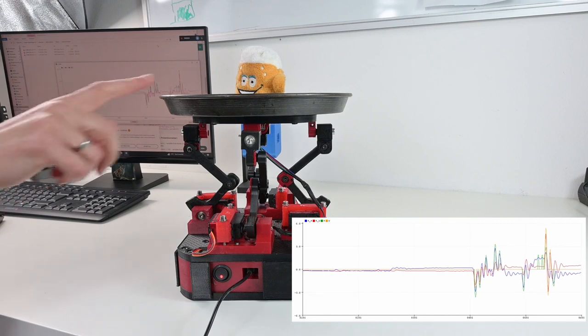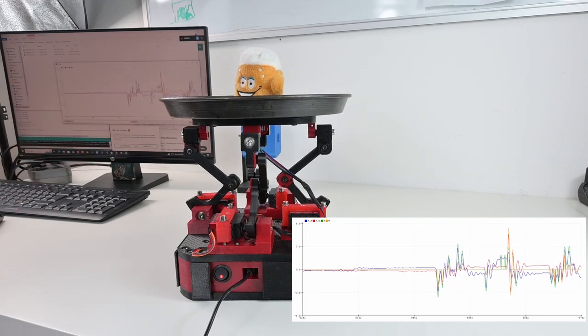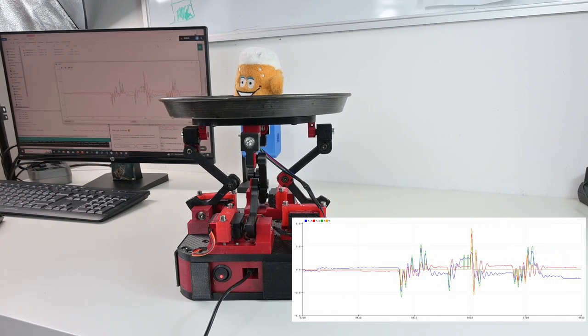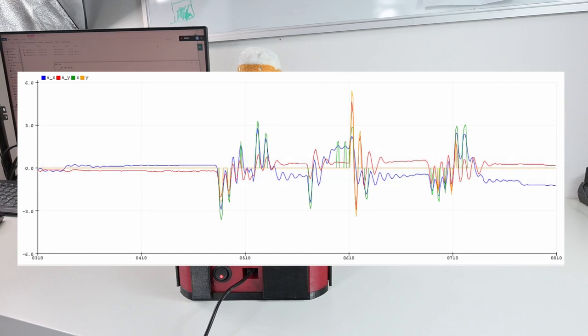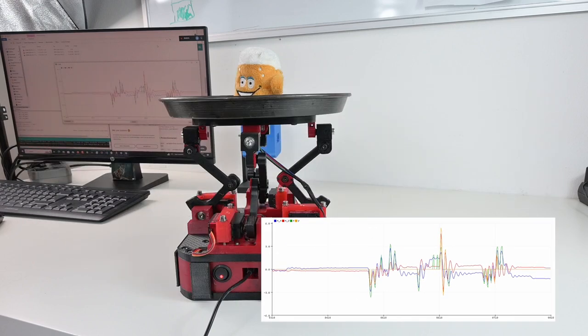As you can see, the wobbling of the upper tray causes a lot of vibrations. To handle those vibrations, a large dead band is necessary. This causes a lot of blind area where the controller is not able to correct the exact angle. A stiffer system could lead to more reliable controlling.